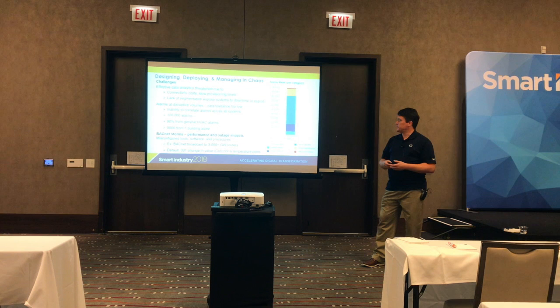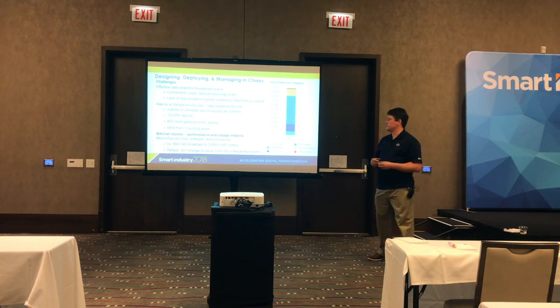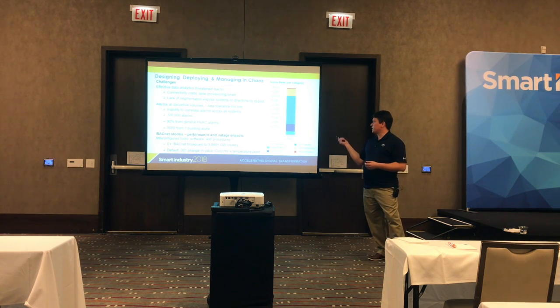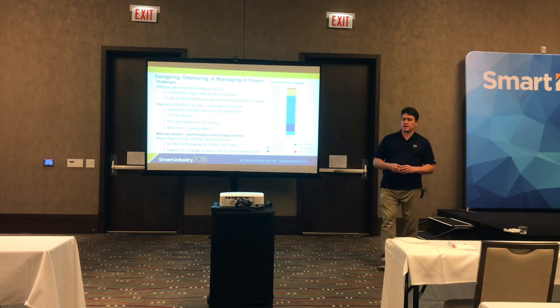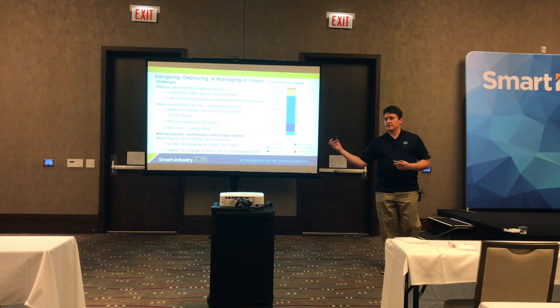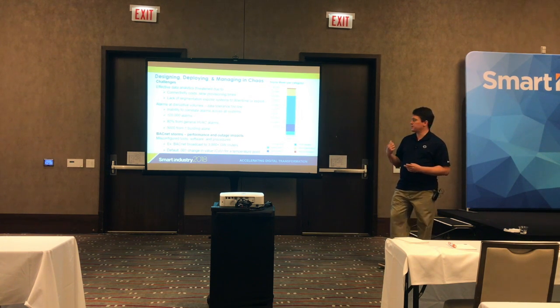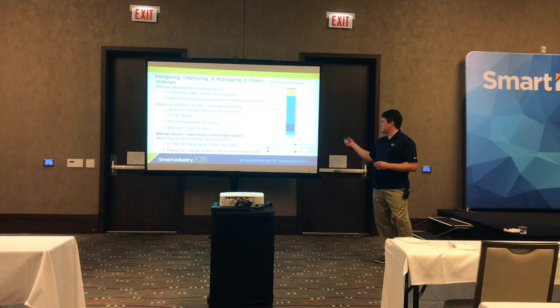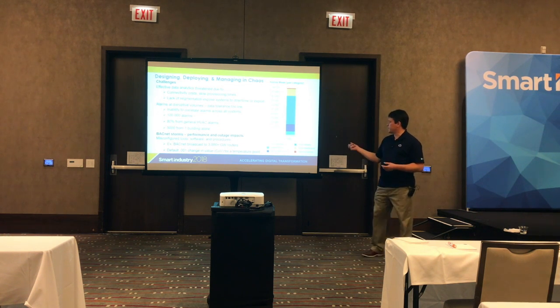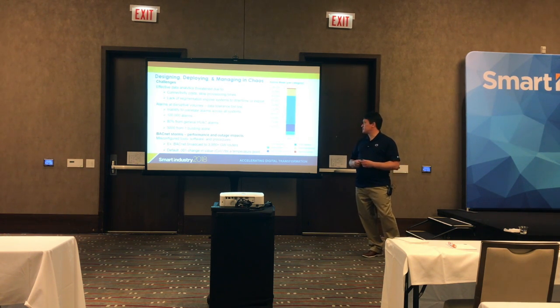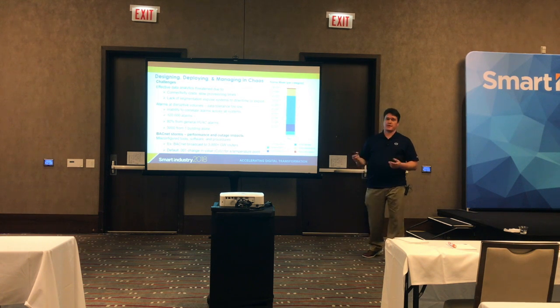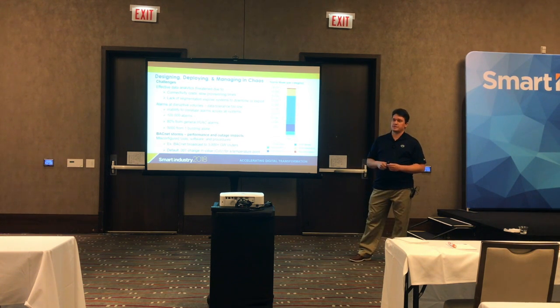One of the issues in the analytics we just started on was alarms this year. In February, I ran a report and started collecting data in a free open source product called Graylog. I was able to take the alarm data from the buildings, upload it into a central system, and start running analytics on it. I found that 80% of our alarms are HVAC general, which are your basic 'I'm out of temp' or 'I'm too low on temp' alarms. That's 80% of our alarms.